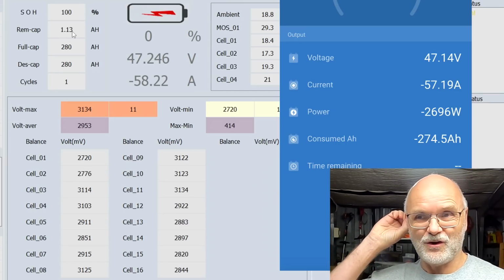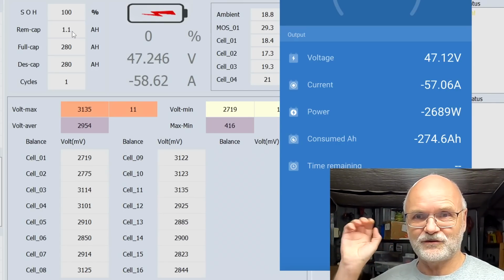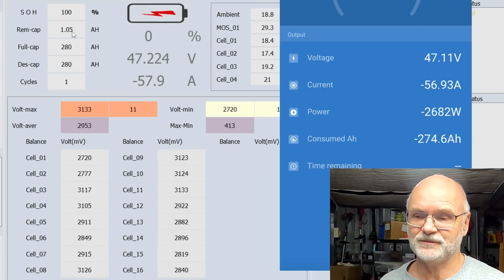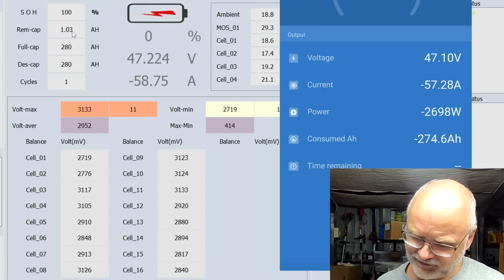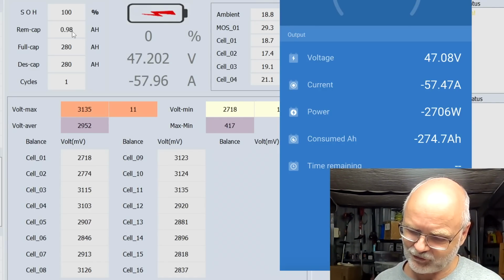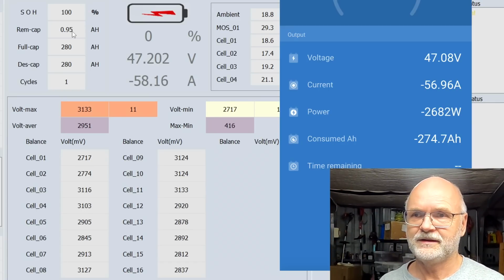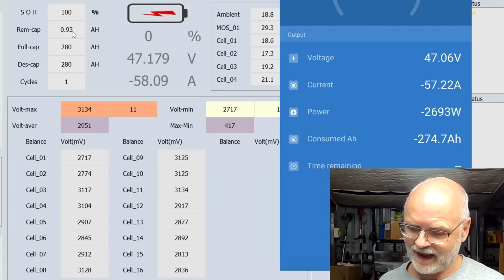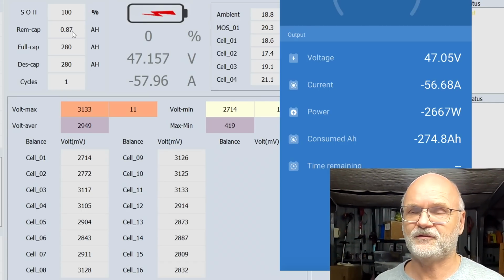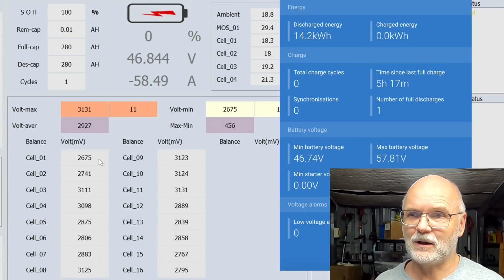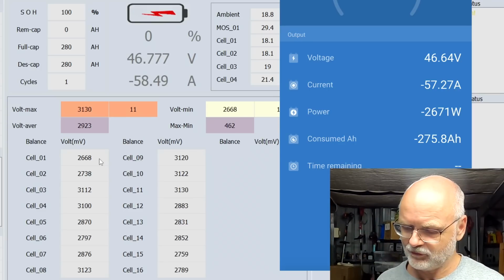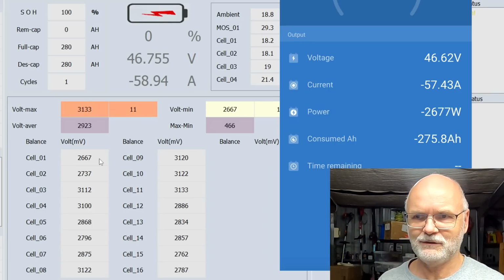1.1 ampere hours to go. The BMS has counted 280 ampere hours, fully discharged the battery, while the smart shunt has counted 274.7. So there's a 5 ampere hour difference, that's fine. Cell number 1 is now in free fall, 2.65 volts. We can reach the 276 ampere hours.